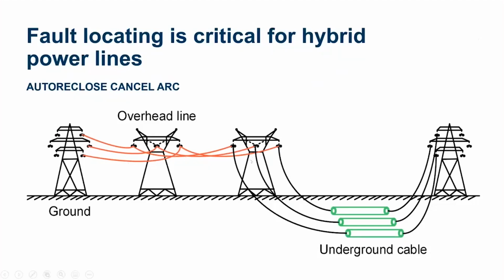Now imagine the second section of the line. This goes over an area that may be prone to wildfires. It goes over some wooded areas and some places that may have a lot of dead trees or a lot of pine needles that will ignite. So on this section you can say, okay, if I see a fault happen in this area, I'm not going to allow auto reclosing. As soon as I see a fault in this area that I've deemed prone to wildfires, I'm going to block auto reclosing. So as soon as we trip, we're going to be driven to lockout. We're not going to auto reclose. So that can save us from reigniting the fault and starting a fire.